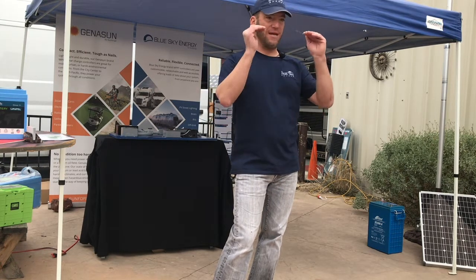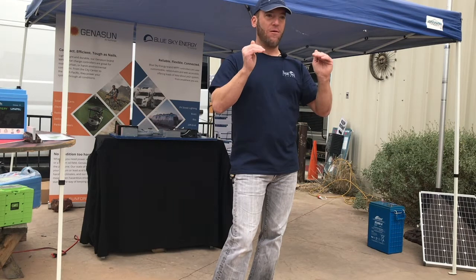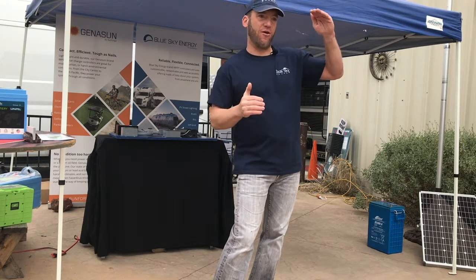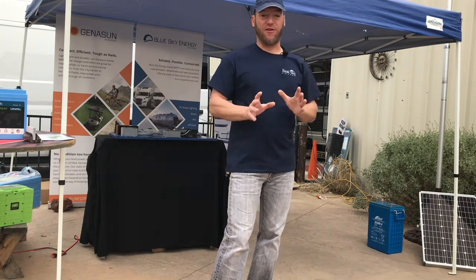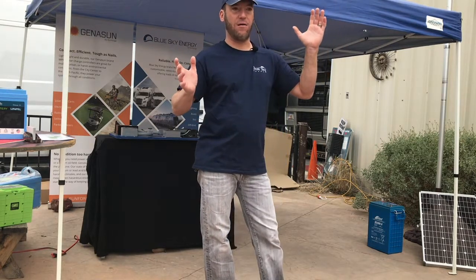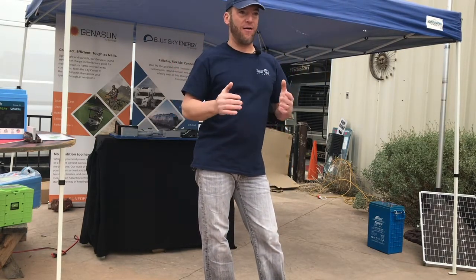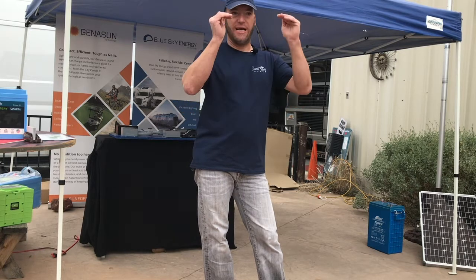So a BMS, when it maintains that top voltage, does what's called top balancing - it'll drain one cell and charge another. Obviously if your cells are completely askew that's not ideal, but in general, unlike a lead-acid battery, the voltages of those cells aren't going to hit the top at exactly the same point.